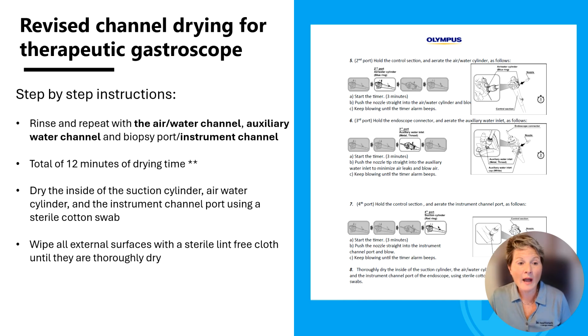Then you're going to dry the inside of the suction cylinder, air water cylinder, and the instrument channel port using a sterile cotton swab. So it's important to make sure you have sterile ones and not the multi-pack, which I don't think are sterile. Have to double check me on that. And then wipe all of the external surfaces of the scope with a sterile lint-free cloth until they are fully dry.